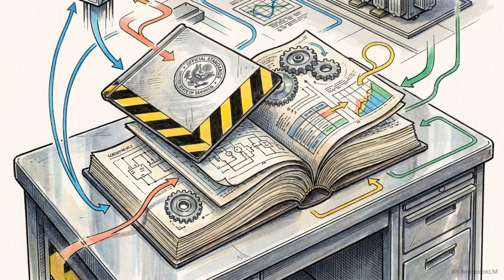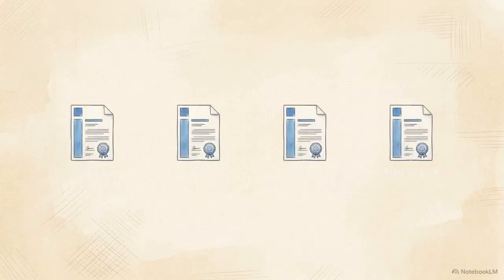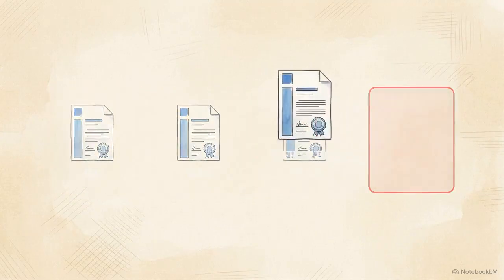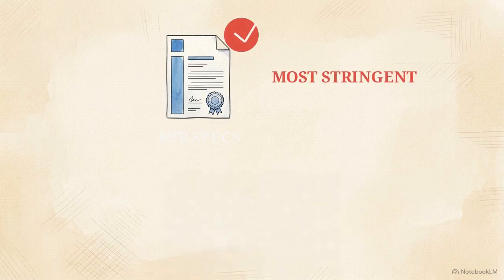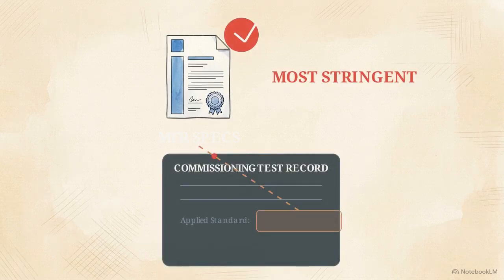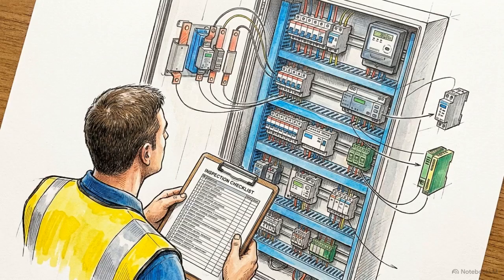Before touching the equipment, we must establish the governance rule for this procedure. When standards from the IEC, IEEE, NEMA, or the manufacturer's own specifications disagree, you must always apply and document the most stringent requirement. Physical prerequisites come first, beginning with a comprehensive visual inspection as dictated by standard operating procedures.